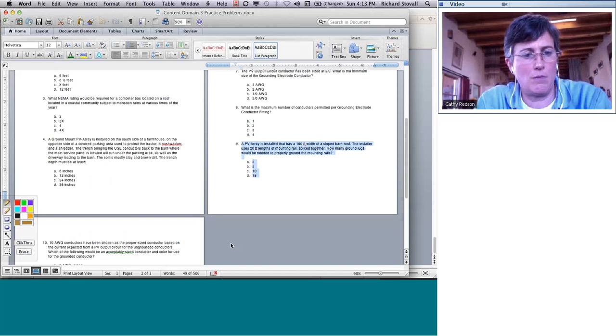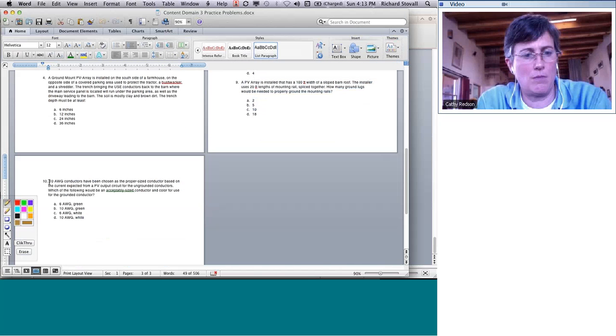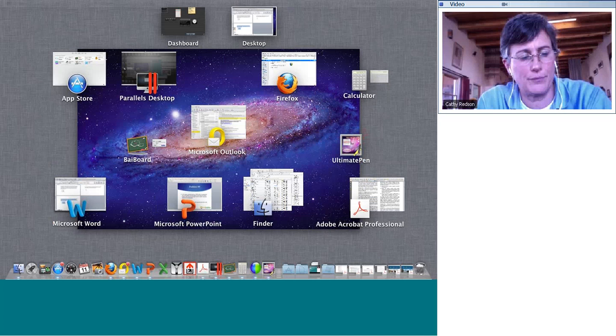Yeah, I have a question. On that question there, I guess for number 7, you didn't size it according to 250.166 for DC grounding electrode sizing. You sized it based on the AC. Why was that?